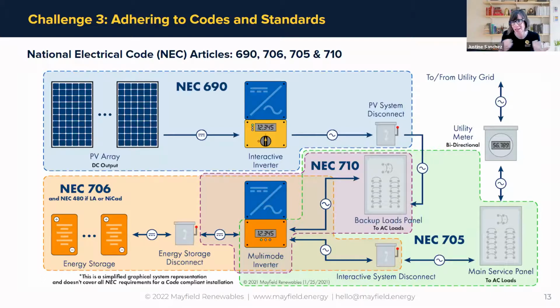And then what if you happen to be working with lead acid batteries? Then the rules of 480 kind of make sense to apply as well, because there are specific safety factors with lead acid batteries, like corrosion prevention and items that have historically been for lead acid batteries that you'll find in 480. So there's a lot to consider when it comes to the NEC, but there's also fire code, which we'll talk about next.